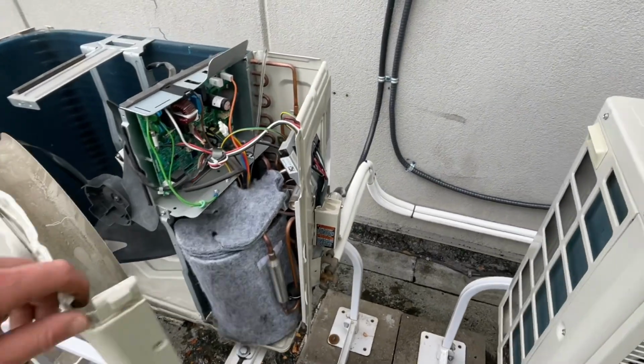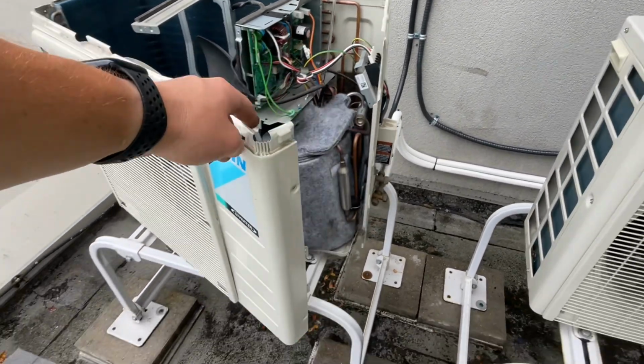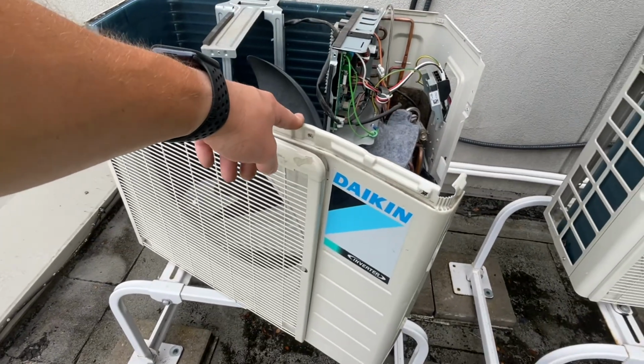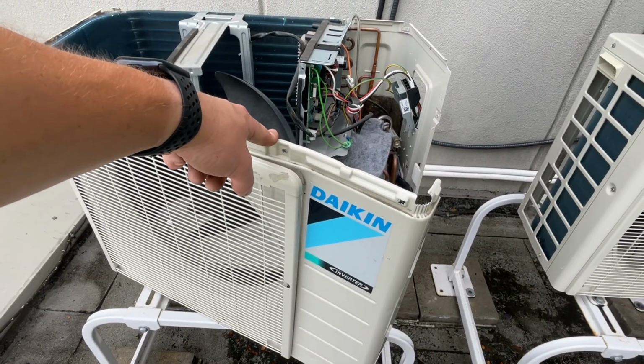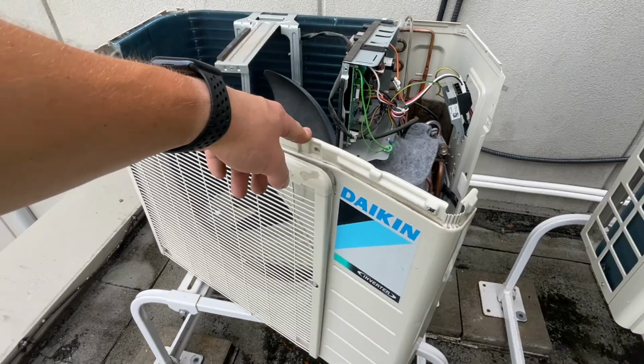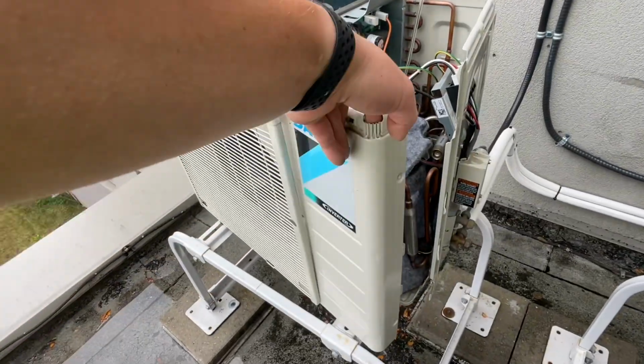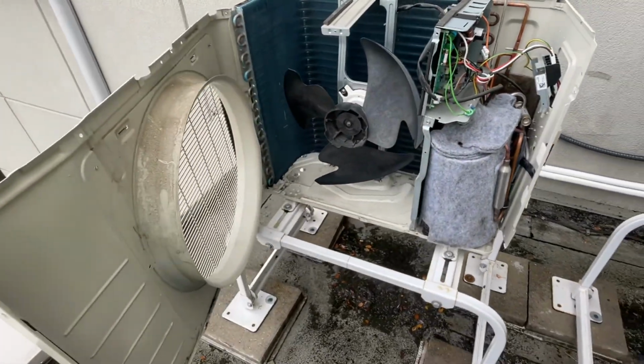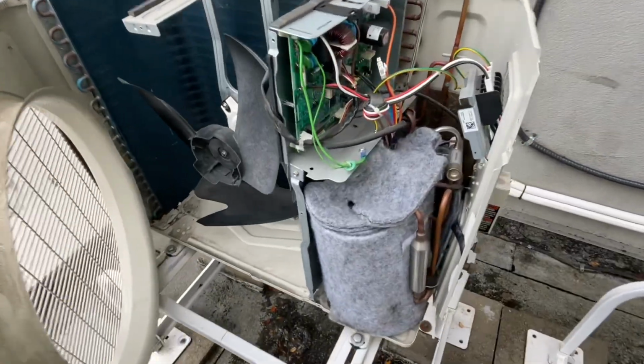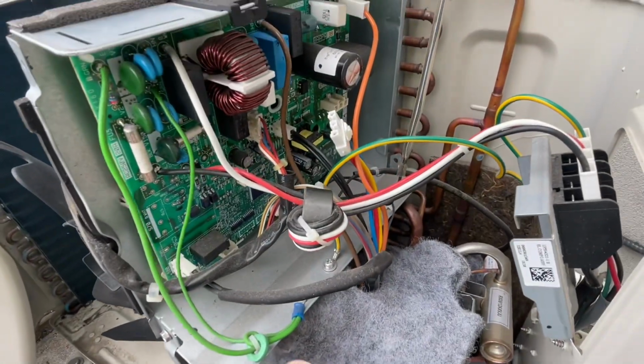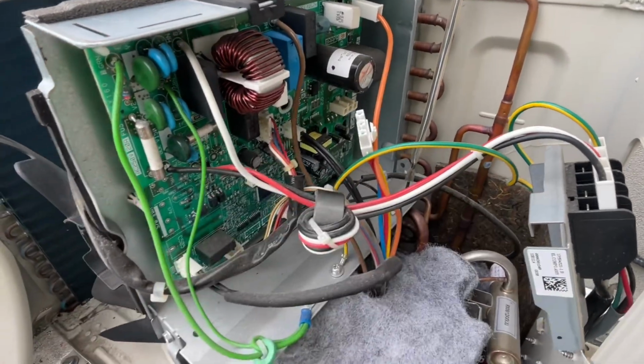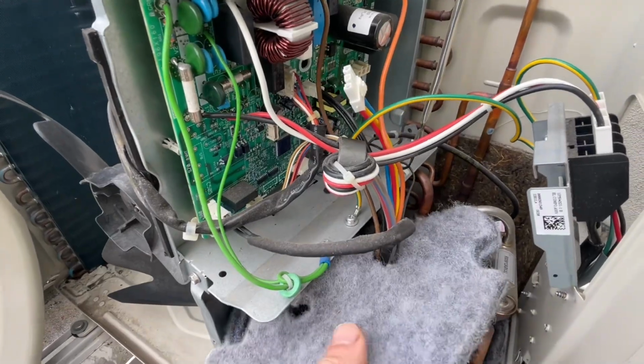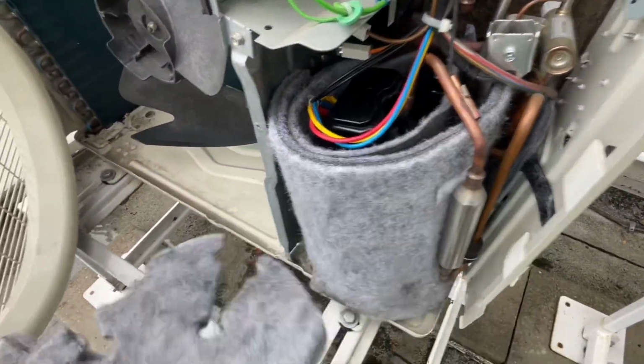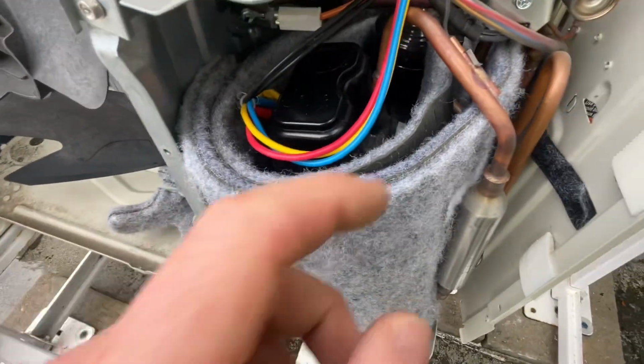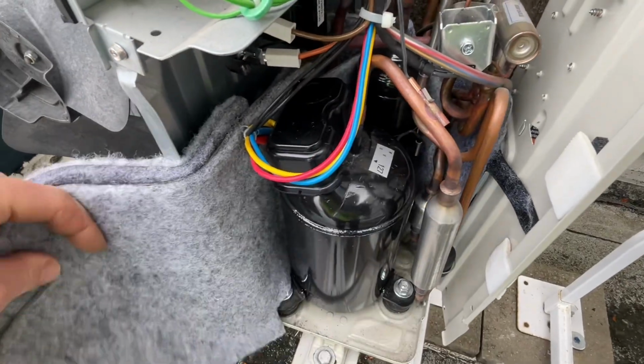What I've done now is I've taken all the screws out. These little systems here are freaking great until they break down. No room to work on these. So you got to take all these screws out. And we're trying to get out our compressor. So I've disconnected it off the board. By the way, I've checked all our connection points. They're good. These are insulated to hell. So we're going to pull all of this back.